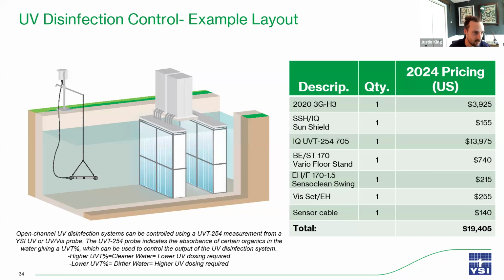And that is going to let the UV channel and the UV lamps know exactly how much intensity of UV light needs to be utilized to treat the water passing by it. So what this control strategy does is it optimizes the amount of energy that is used to effectively clean the water. So if the UV transmittance is higher, that indicates that the water is cleaner.